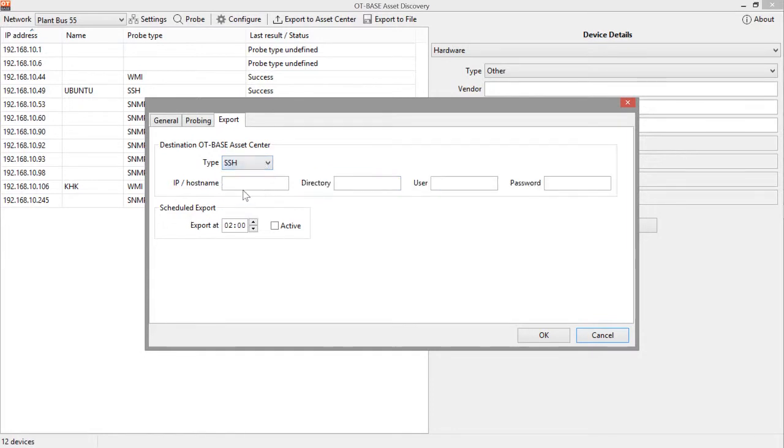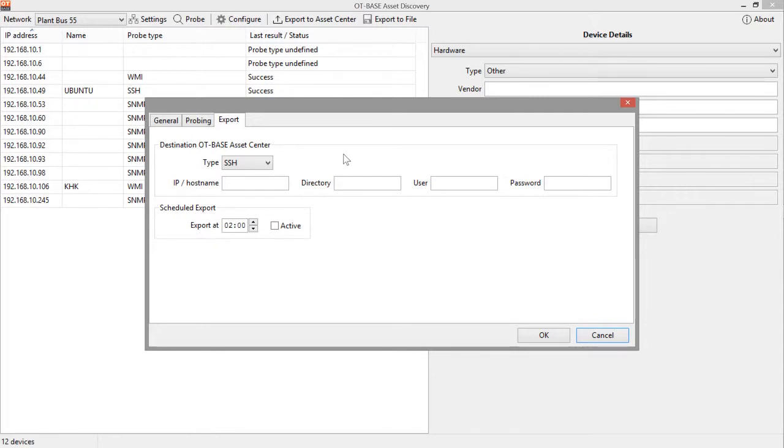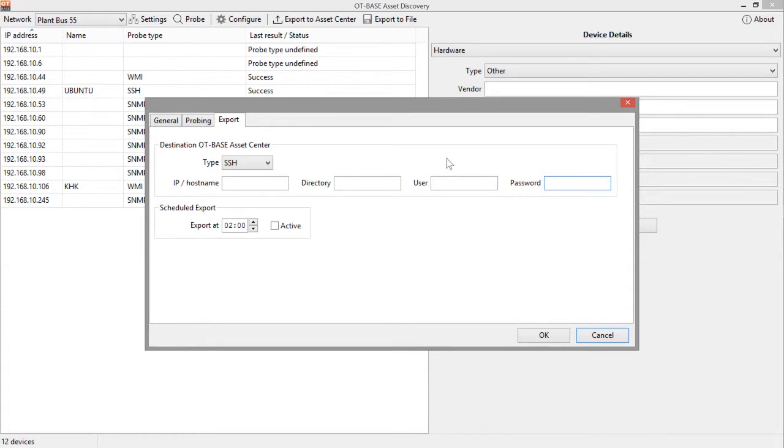Next option is an SSH link. Again this would apply if you cannot reach the OT-BASE asset center directly. In this case you can transfer configuration data using SSH to an intermediate server, provide the IP address or host name in this field, any path or directory information in this field, and user and password required for authentication for the SSH link.